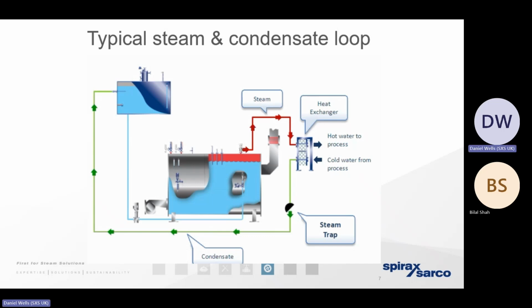Now, when steam gives up its heat energy, it condenses. That basically means it changes state from a gas to a liquid, so its volume collapses significantly. When that happens, the steam gives up its heat energy, it changes state from a gas to a liquid, but it doesn't cool down. So that condensate exists at exactly the same pressure and exactly the same temperature as the steam. It's just got less energy in it. And condensate's a byproduct, it's unwanted. We need to get it out of both the distribution pipework, and we need to get it away from the bottom of the heat exchanger as well.